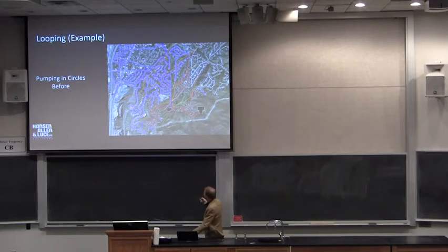But it got even worse. If you trace that water, we're tracing the water that went through that pump station. It's actually falling down the hill, falling down the hill. It got all the way to the bottom. And then it would pump back up. So this was a common way of how they operated the system all summer long.